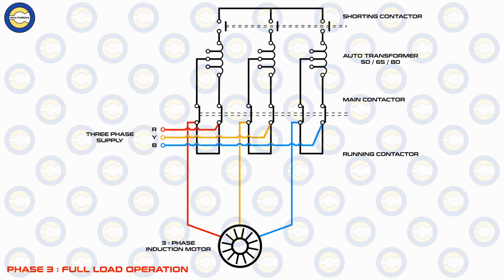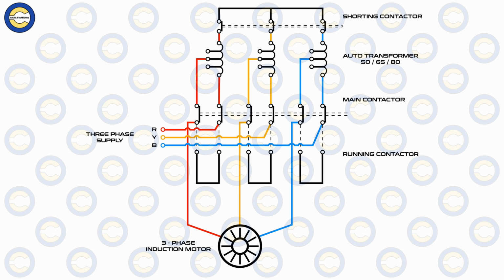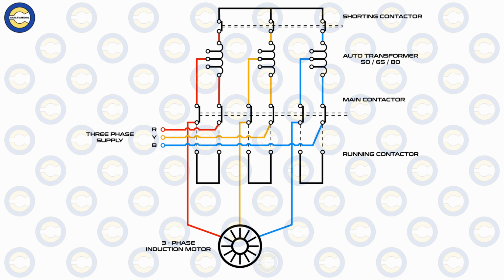Now that we have explained the working and the circuit orientation, a very common question that arises in your mind is how the tappings for the auto transformer design change. In an auto transformer type starter, the primary and the secondary windings share a common winding. The tappings are taken along the continuous winding to obtain different voltage ratios. As I had said earlier, for example 50, 65, 80%, etc. values. So these are the tapping points that allow adjusting of the starting voltage.